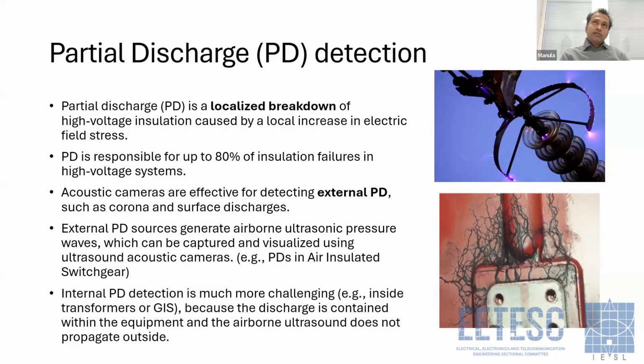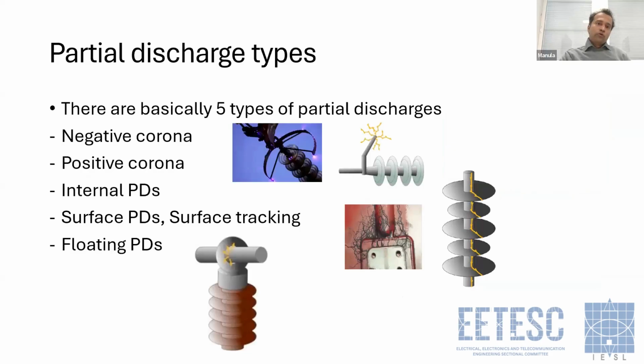These internal partial discharges, of course, would generate ultrasound, but it would not be emitted into the external environment as airborne ultrasound, so it is not very practical to detect this kind of partial discharge by using ultrasound cameras. Okay, so now we know what partial discharge is, and let's jump into what kinds of partial discharges there are. There are different types of partial discharges.